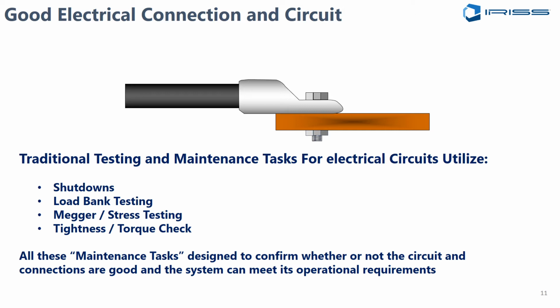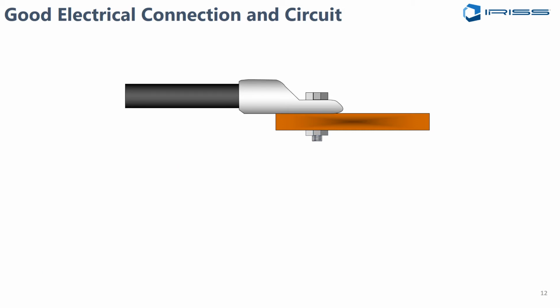So this is why we do this shutdown and this testing, but it's antiquated. You can only tighten a bolt or a screw or a nut so many times before it breaks. And we've seen people tighten the connection because they think it's a loose connection, but it's not. It's a lug or something else that's causing the issue. So there are better ways that we can do this.